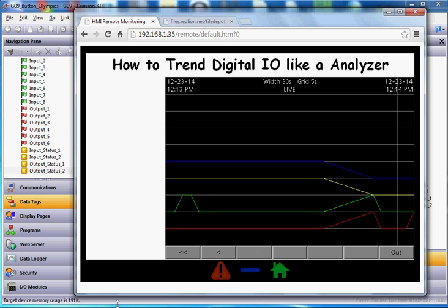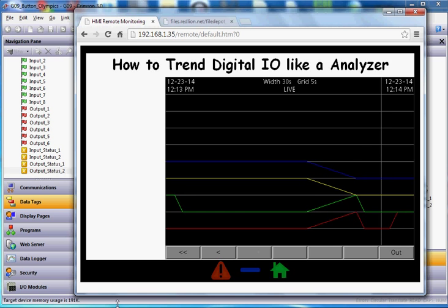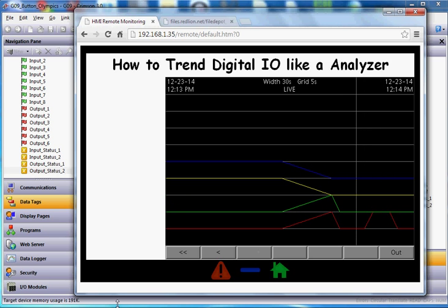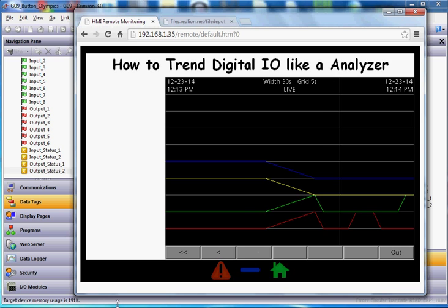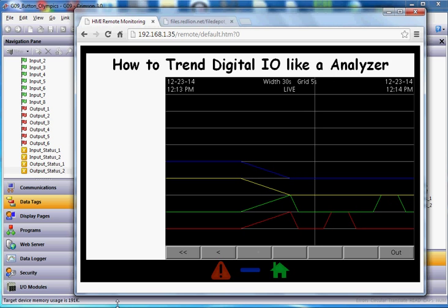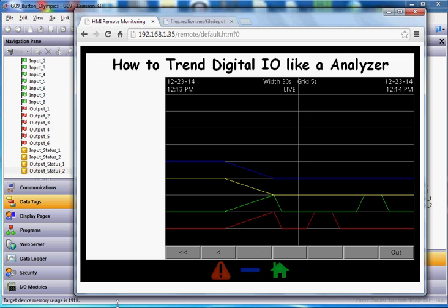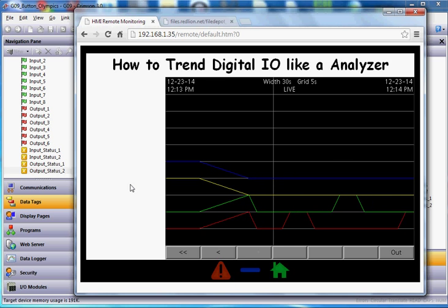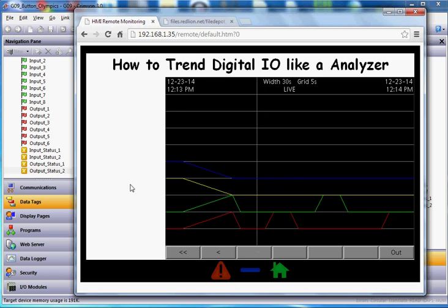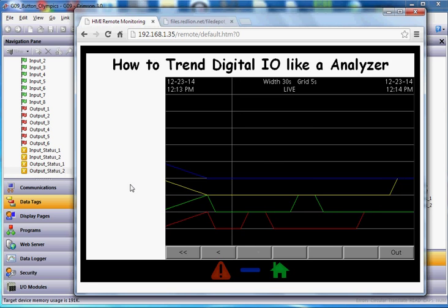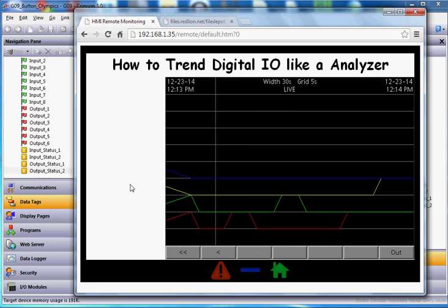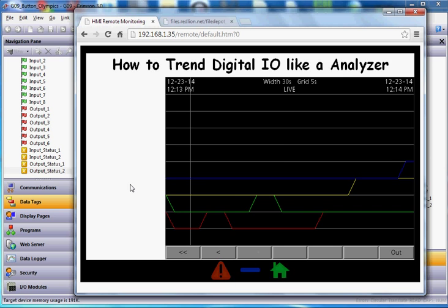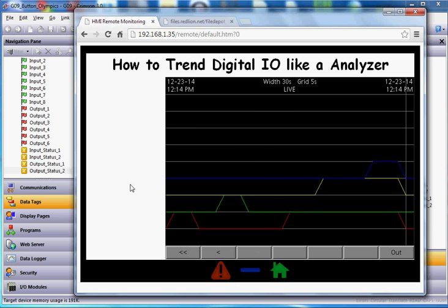If I hold on my input one, you can see it trend across there. If I turn it off and then go hold on my input number two, you can see the green line trends across there. And the other logic I got running on here is if I hold on my input number one for more than five seconds, the first output should go on, and you can see that right there. And then if I continue holding it to ten seconds, output two goes on, and there it is. And then once I turn this off, all the outputs should go off. Perfect.